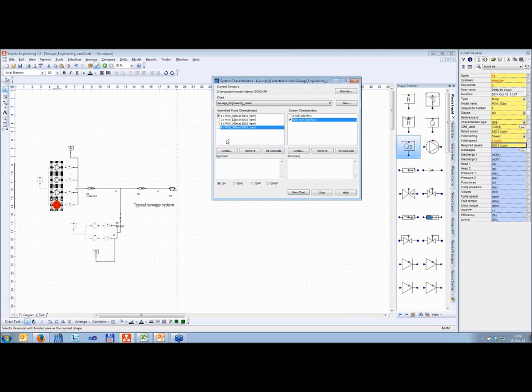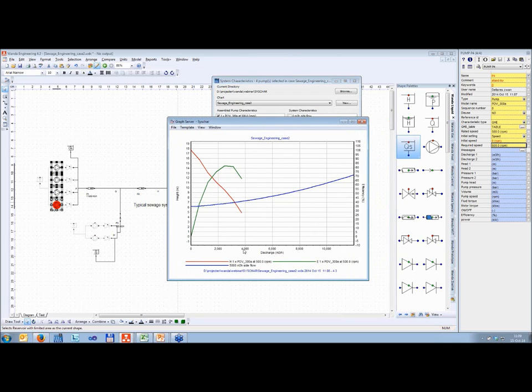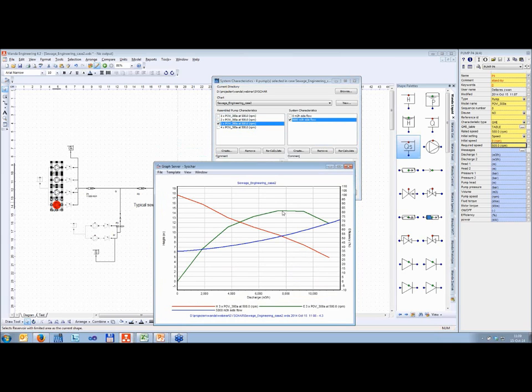Let's look at only one pump. You can also select to include the efficiency curve — the QHE. If I plot it, the green line is my efficiency curve. I can easily see this is my operating point, and I'm a little bit to the right of my best efficiency point, which might not be acceptable. You can see that already in these easy steps. You can also do it for three pumps, and you can see this is nice — it's at the best efficiency point, so that's a good operating point.